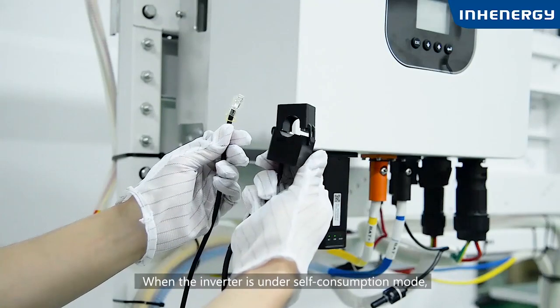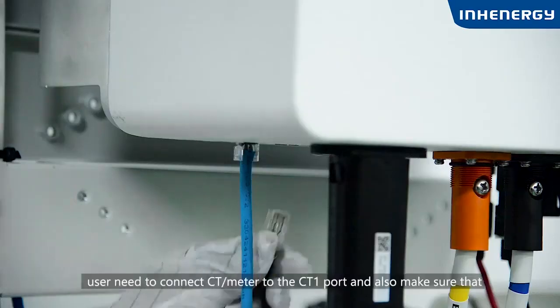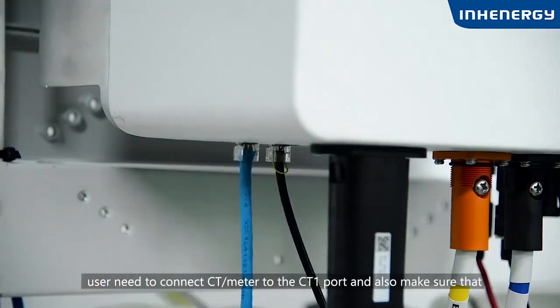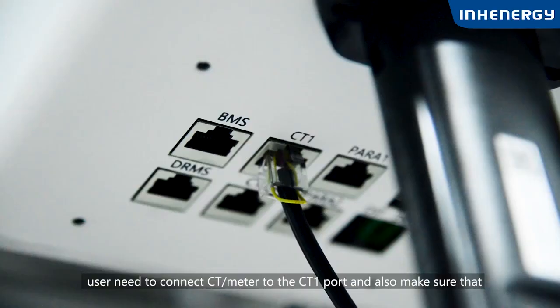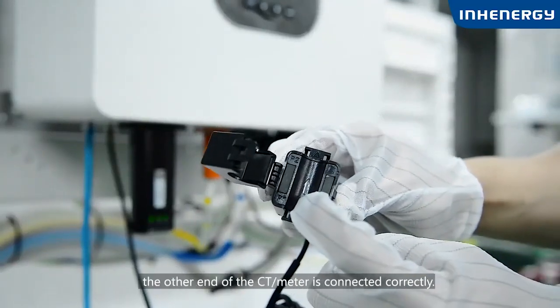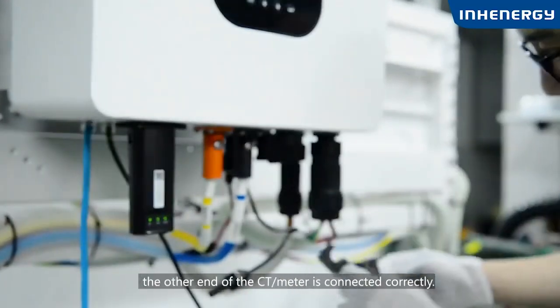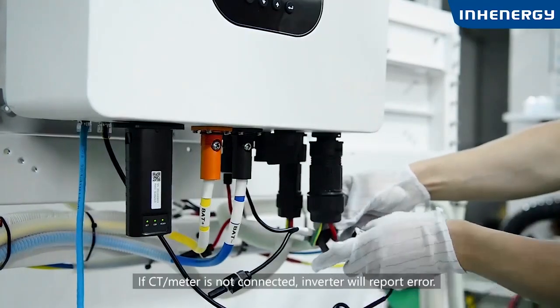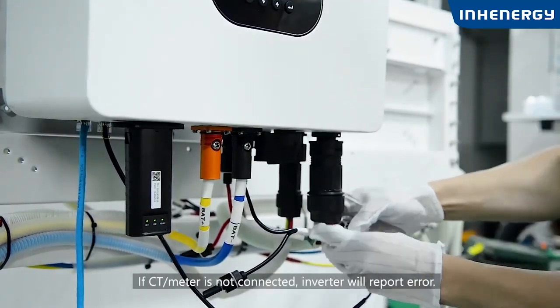When the inverter is under self-consumption mode, user needs to connect the CT or meter to the CT1 port and also make sure that the other end of the CT or meter is connected correctly. If the CT or meter is not connected, the inverter will report an error.